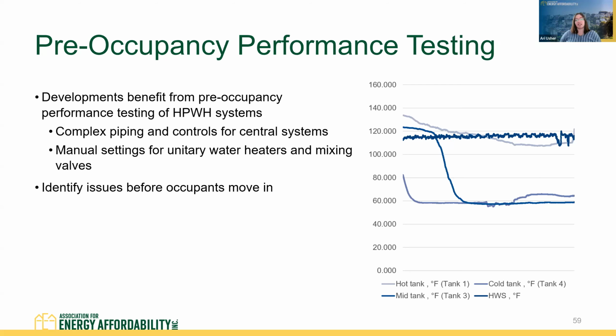This is going to allow for the identification of issues before occupants move in. Nothing worse than getting occupants in and all of a sudden there's a whole bunch of hot water complaints. AEA, we've worked with projects to actually do some pre-occupancy performance testing, and with installers to develop some kind of stress testing on these systems. And we would be more than happy to work with anyone that's got a project to develop some performance testing procedures, if that's something you're interested in. So we could do that potentially through our no-cost technical assistance offering CalEHP has, and I will hand it to Erin to talk a little bit more about that.